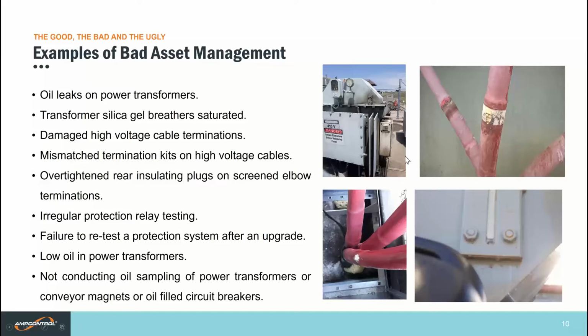Going on to the photos that we've got up there on the screen. As mentioned, a transformer, fairly badly stained. It may only be a minor leak that's possibly a lid bolt that's come loose or around the sight glass. Could even be where the temperature indicator has been put into the transformer and may not be tight enough. Next, the photo on the top right shows how badly the tracking can be across a PVC tape that's been put onto an 11,000 volt cable. While it indicates what phase that is, it's not the best way to go.